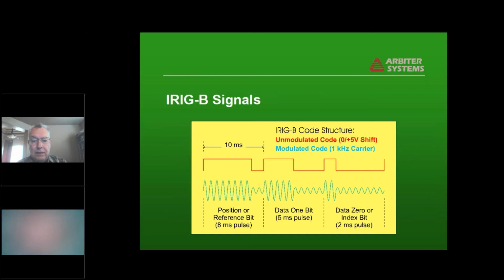This is what IRIG-B signal looks like. It's a 100 bit per second, 10 millisecond frame, and it has a modulation which depends on the width of the pulse. The wide pulse there you see is basically a position or reference bit that's used for framing. The data bit for 1 is 5 milliseconds long or 50% duty cycle, and a 0 or index bit, anything that's not a data or position bit, is broadcast with a short pulse of 2 milliseconds.